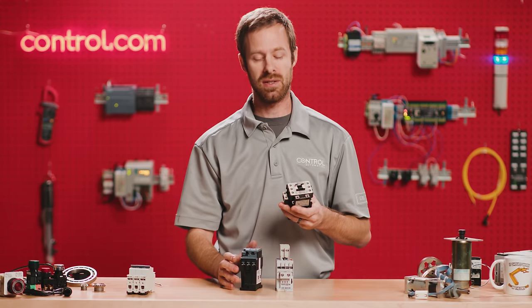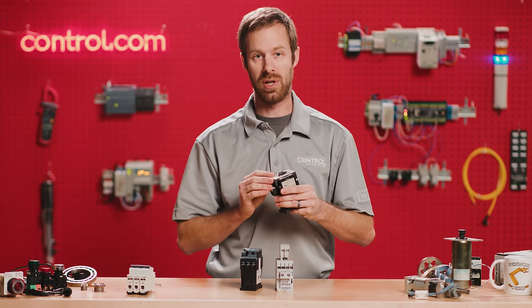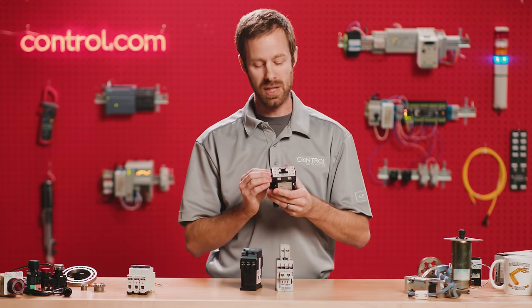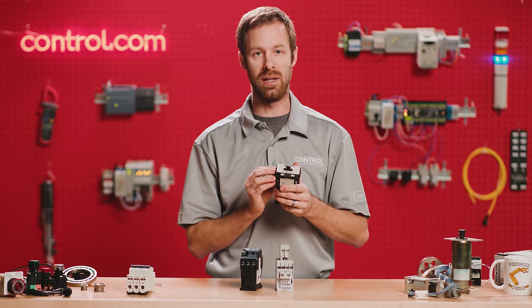The first of these sets of contacts is what they call the main contacts. There are usually three of them on a motor starter for three-phase electricity to supply to the three-phase motors. These main contacts energize and engage anytime electricity is supplied to the coil.